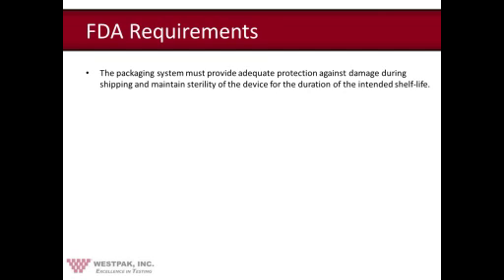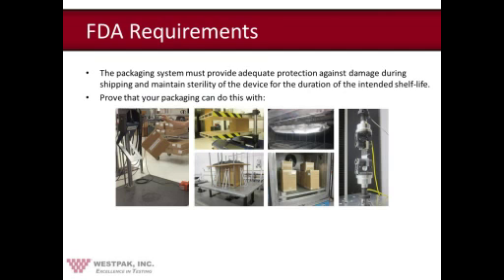And what they're actually looking for is pretty straightforward, but it's also a little vague at the same time, since they don't actually provide too much guidance on it. The FDA pretty much says that the package system must provide adequate protection against damage during shipping and must maintain sterility of the device for the duration of the shelf life. And they say to prove this package validation with testing. Prove that your package can withstand the shipping and distribution environment and maintain sterility.